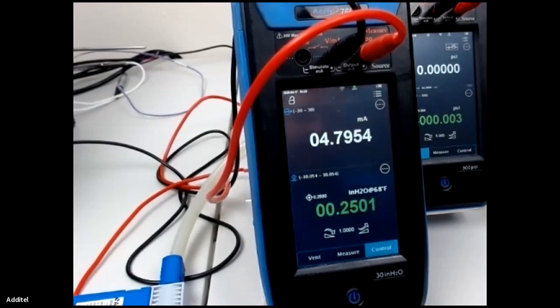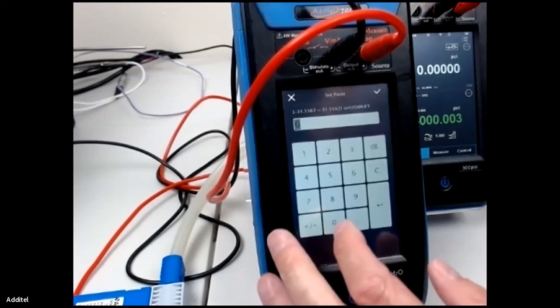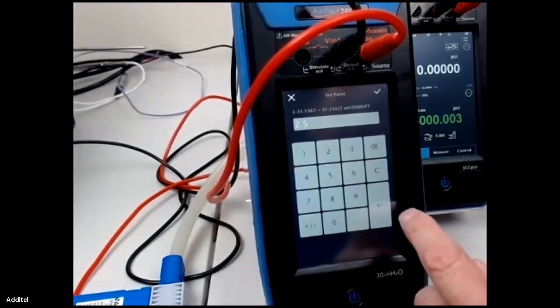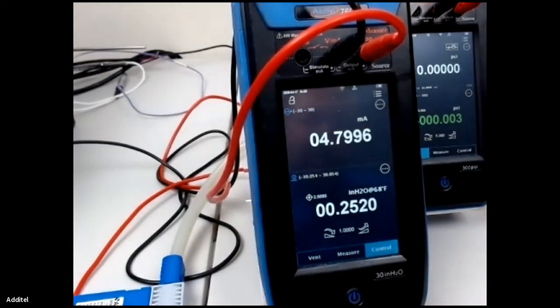We're also reading the milliamps as you can see here. So let's say I wanted to go to 2.5 inches of water, that would be roughly half of the 4 to 20, should be about 12 milliamps. We'll go ahead and take it up there real quick and show you guys how that performs at the midpoint.